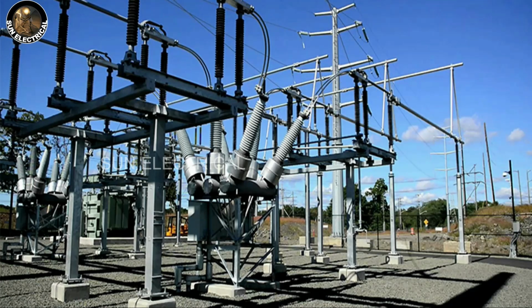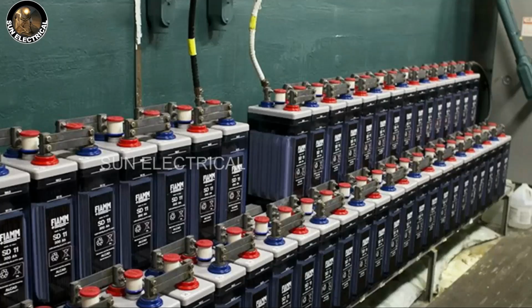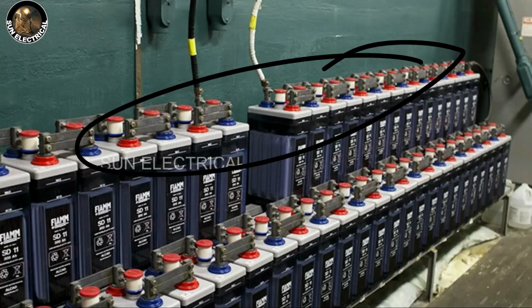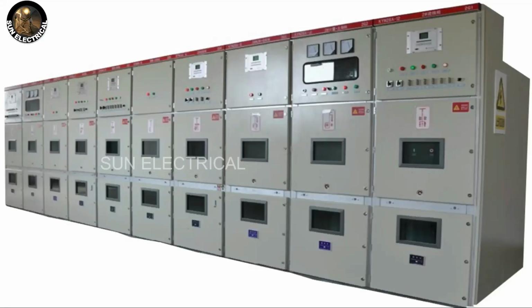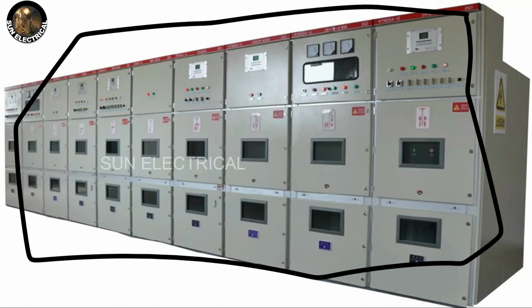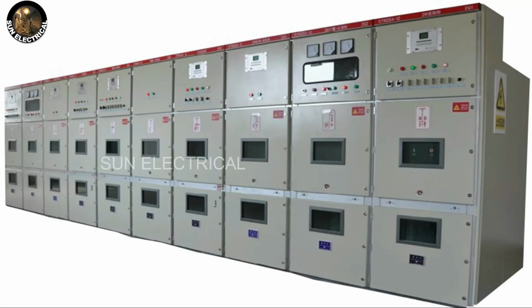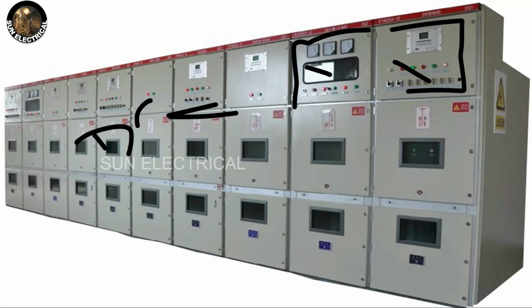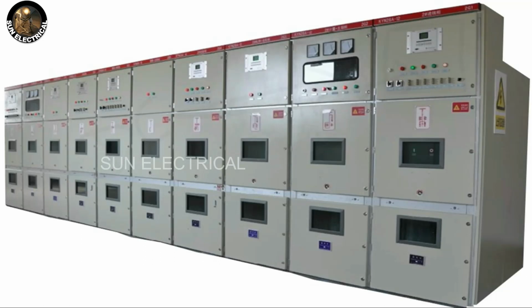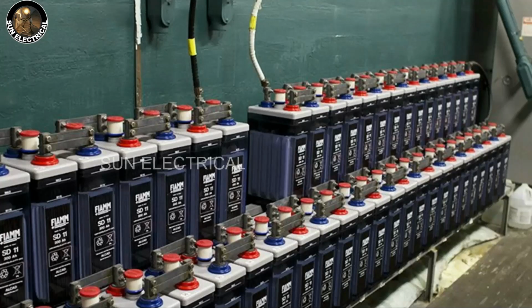The main reason for using DC supply in every substation or power station is to provide a continuous power supply to the control panel or control circuits. This is a control panel, for example an MCC or PCC panel, and we provide these panels only DC supplies. DC is a reliable source of power supply because it can be obtained from batteries. Only a battery can give continuous power supply until it fully discharges. The battery has electrical energy storing capability, that's why it can be used for backup power supply.